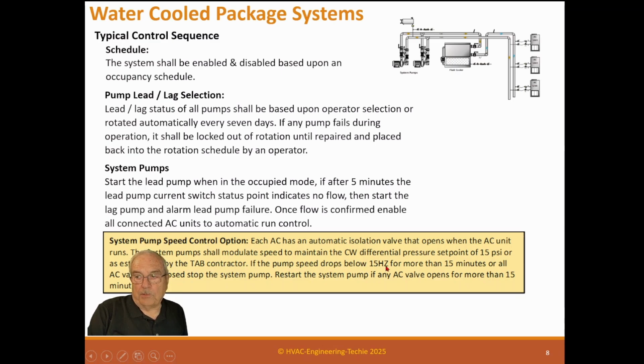If the pump speed drops below 15 hertz for more than 15 minutes, or maybe 12 hertz, that's all adjustable, but you can't go too low because the motor windings need cooling, and the fan of the motor provides that cooling, unless you have a true VFD motor that has a separate motor for cooling, and most of them don't. So you can't go to zero. You can't go off because you'll heat up the windings and it'll burn the motor out. If it's down at 12 to 15 hertz for more than 15 minutes and all the AC valves are closed, then stop the system. Restart the system pump if any AC valves open for more than 15 minutes. Now, these timers give us some slack so we don't short cycle any system. So it takes 15 minutes, then it'll come on. That way, the temperature's heated up a little bit. It'll have a little bit more load for that time.